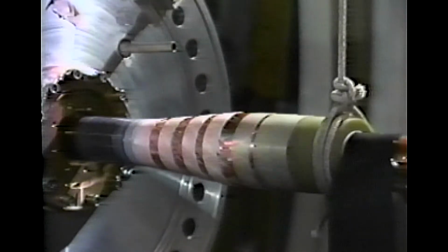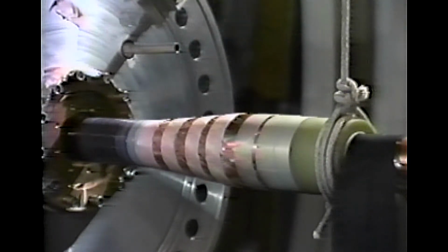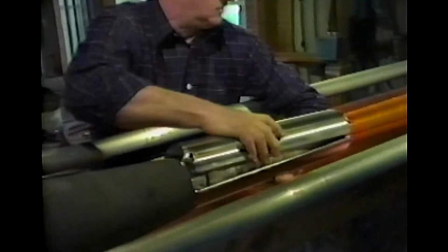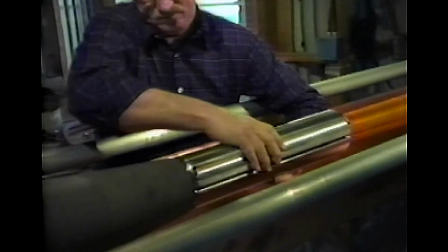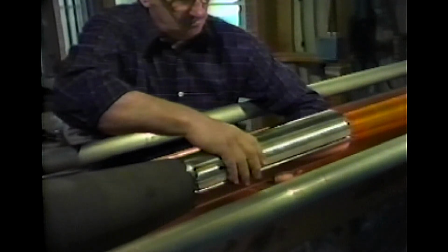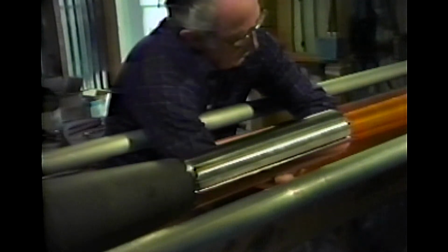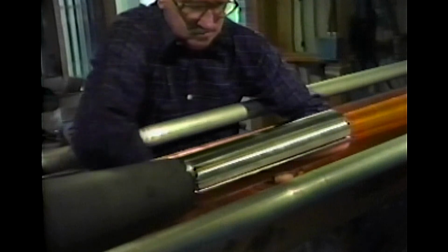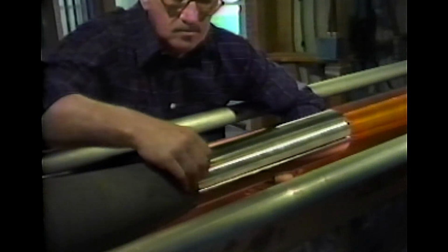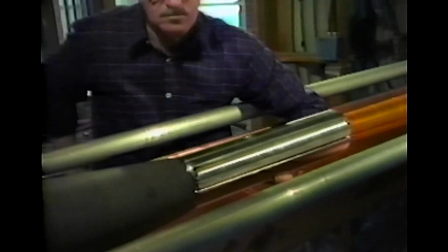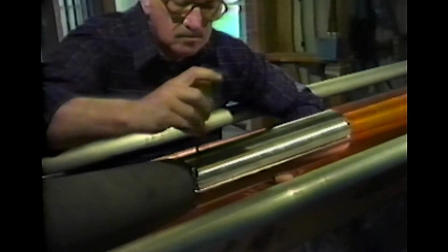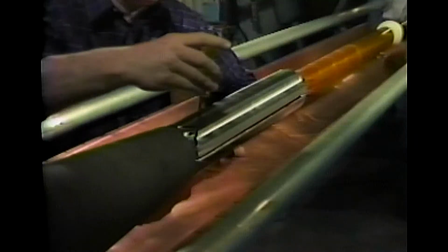A completed cable end awaits the next step in the assembly of the termination. The termination design posed a challenging problem. It must carry the same voltage and current as the cables themselves, but at the same time operate with a temperature difference between one end and the other of about 540 degrees Fahrenheit.